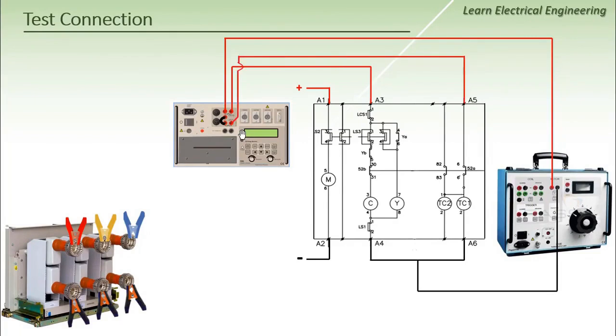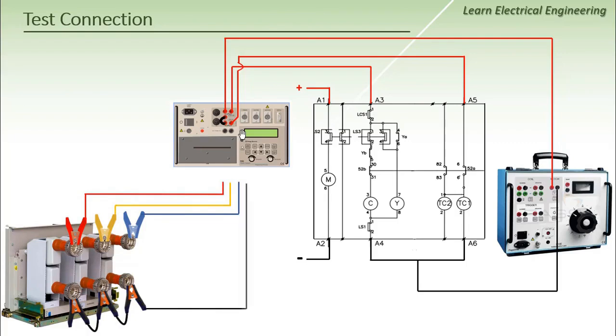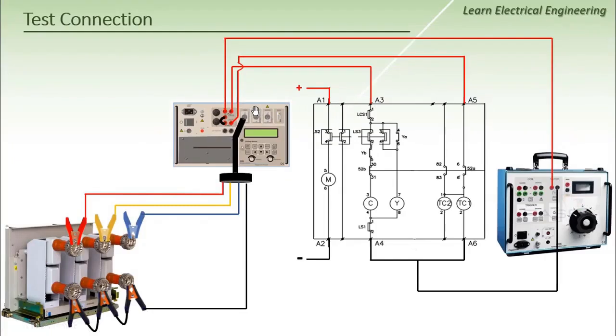As for the primary circuit, I need to take my feedback from the main poles of the circuit breaker. I have a special cable that comes with the Aegis device, which is the breaker analyzer, and it has 4 terminals: L1 terminal, L2 terminal, L3 terminal, and a neutral terminal. I connect the 3 terminals, L1, L2, L3, to the 3 poles of the circuit breaker. Then I connect the other ends of the poles of the circuit breaker together with a jumper and output a single terminal, which is the neutral terminal. Finally, this cable is gathered and connected to the terminal labeled timing on the Aegis device. And with that, I have completed my connection setup.